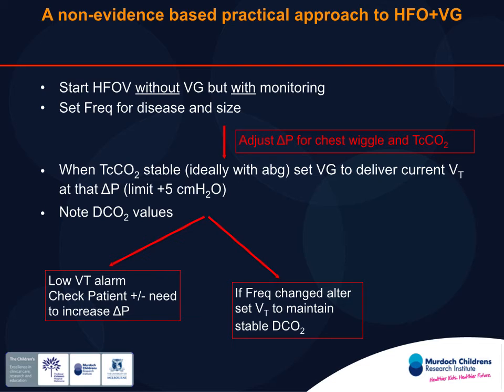So yes, these are the settings which give me the CO2 I want, which is what we've been doing for decades. Then think about volume guarantee. So go, okay, I've got the CO2 I want. What delta P and what tidal volume has achieved that? That should be my initial volume guarantee setting, not something that you've been told to do by somebody. Set your delta P limits sufficient enough to allow for change, because that's the whole principle of volume guarantee. It allows the ventilator to change pressure, but it will only do so within the constraints you have.